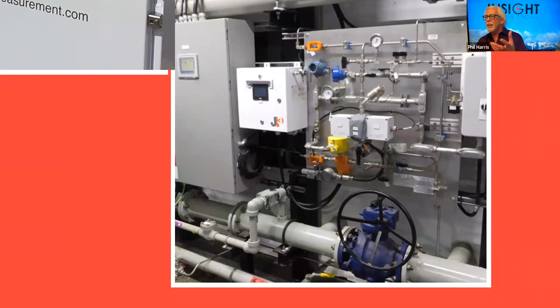So the skid, or panel, that you see right here is at a crude oil blending skid. You can see the 4-inch pipe running over the top and bottom. In the middle, the white box is a little JP3 analyzer. The box with the gray covering is where the near infrared cell is. We're flowing a sample of the crude oil through that cell and doing real-time measurements of vapor pressure.